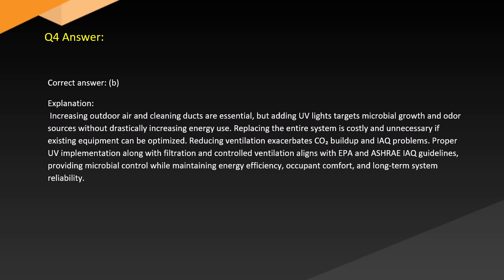Increasing outdoor air and cleaning ducts are essential, but adding UV lights targets microbial growth and odor sources without drastically increasing energy use. Replacing the entire system is costly and unnecessary if existing equipment can be optimized. Reducing ventilation exacerbates CO2 buildup and IAQ problems. Proper UV implementation along with filtration and controlled ventilation aligns with EPA and ASHRAE IAQ guidelines, providing microbial control while maintaining energy efficiency, occupant comfort, and long-term system reliability.